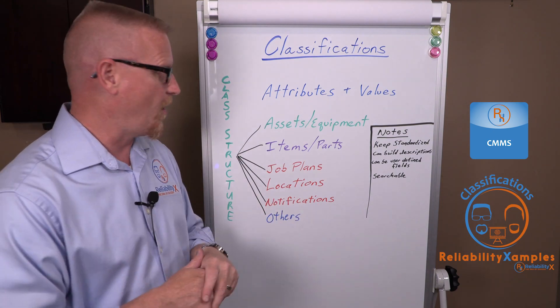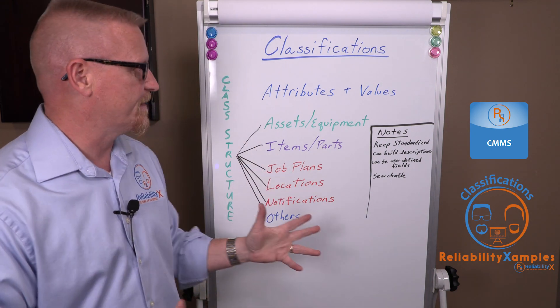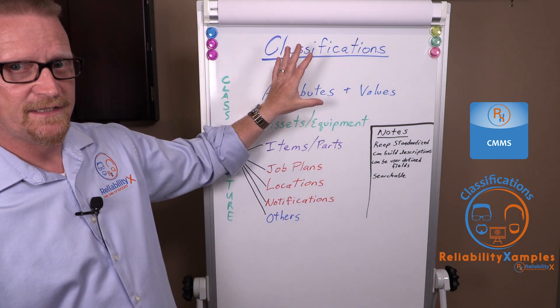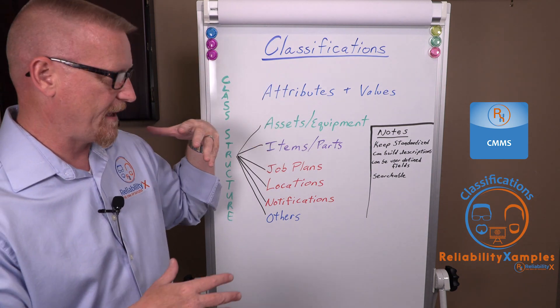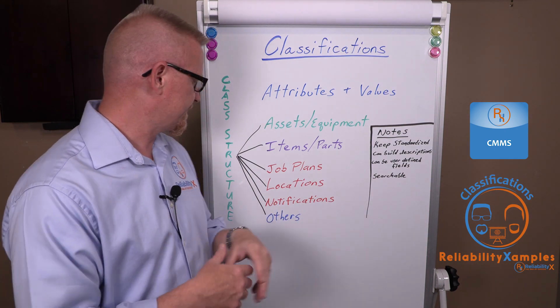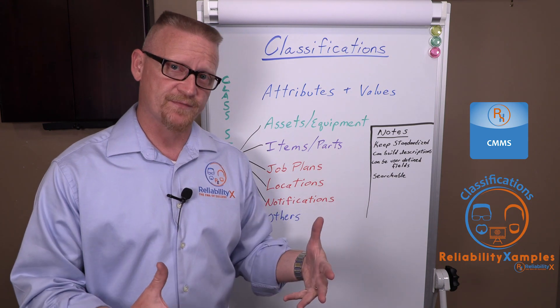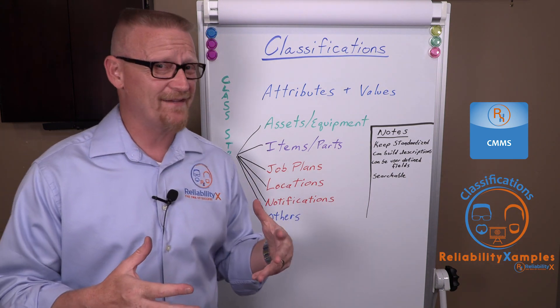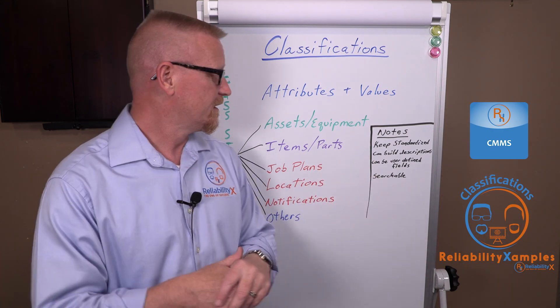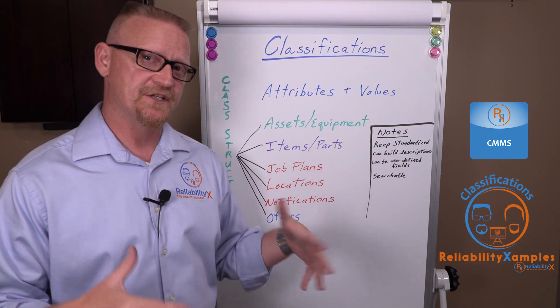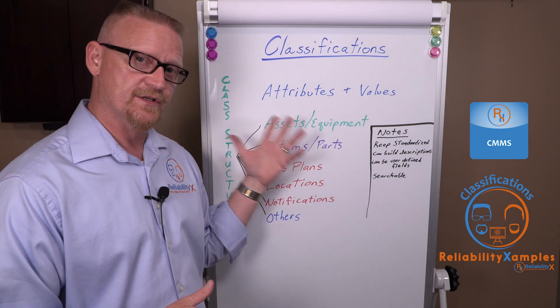There are a lot of unique scenarios around classifications. A couple of things to keep in mind: keep standardized naming conventions for your classifications and make sure you don't have multiples or duplicates of the same type of assets. Classifications can also build your descriptions — instead of having 800 inventory items that just say 'bearing', if you populate your classification attributes, that attribute list can become the description.